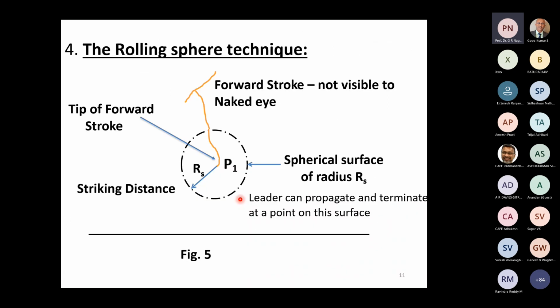Now again, we use the rolling sphere. We think of the principle of the rolling sphere technique for practical application. So again, we have seen here that the leader has come down, of course, in a rugged path to point P1. Let's say that because of the specific prospective current in the stroke, the striking distance, or the next step distance, is Rs. As I've been telling you several times, the leader can develop in any direction onto this spherical surface at the same distance. It has the capacity to hit this distance because of the prospective current magnitude in this stroke.